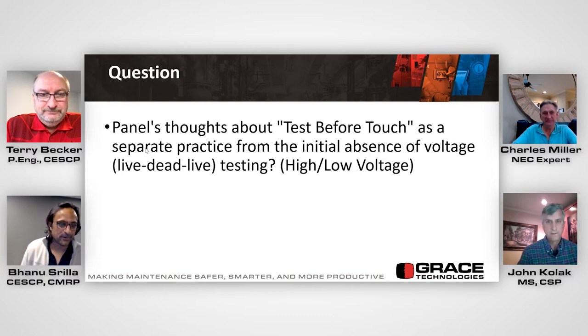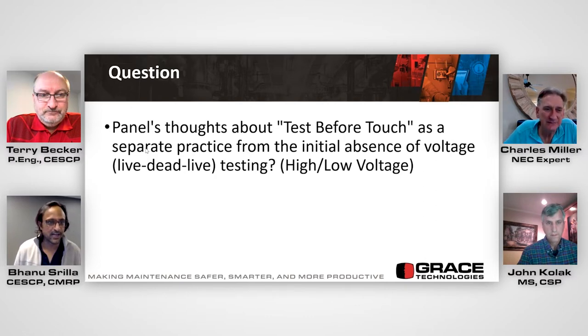So do you propose the 70E revise the language to add personal protective grounds even for low voltage systems? Well, actually, grounding is superior to lockout tagout. If you actually have a full set of grounds on, it's wonderful to have. It's just that most low voltage systems can't accept them. So you're mostly just grounding transformer secondaries. But having said that, anytime you can get yourself into a safer position, I would do that.